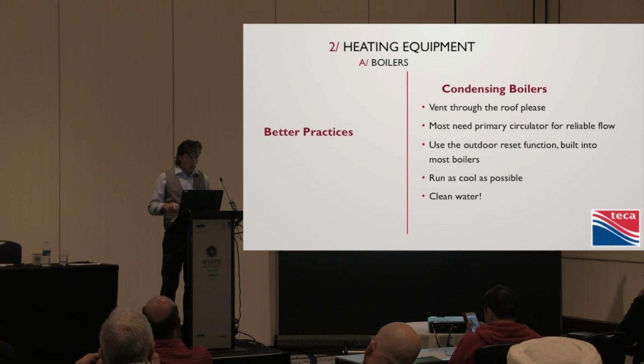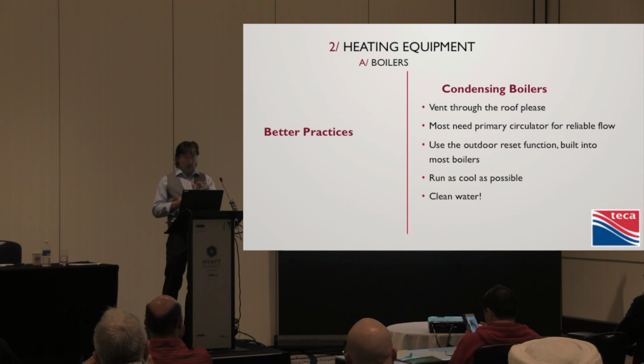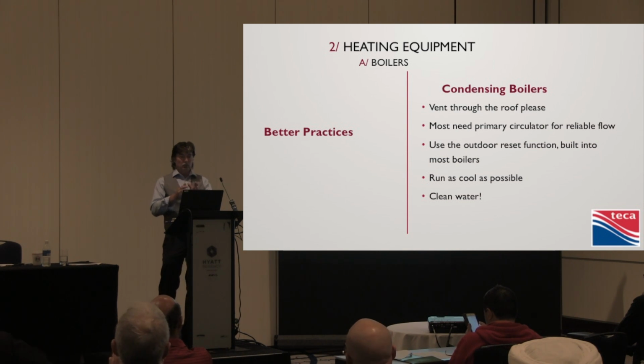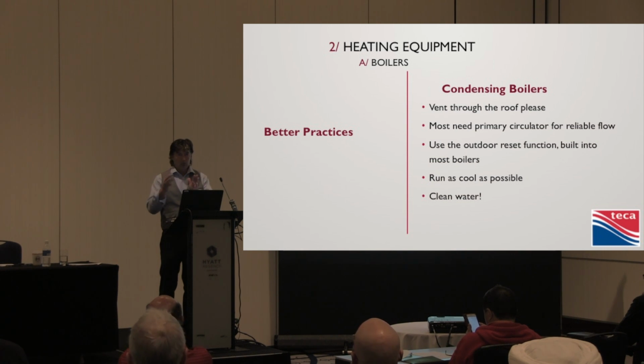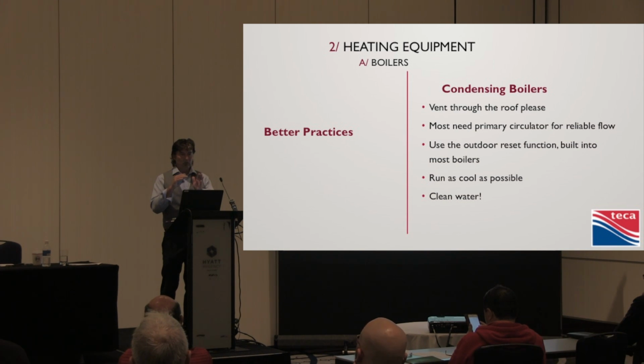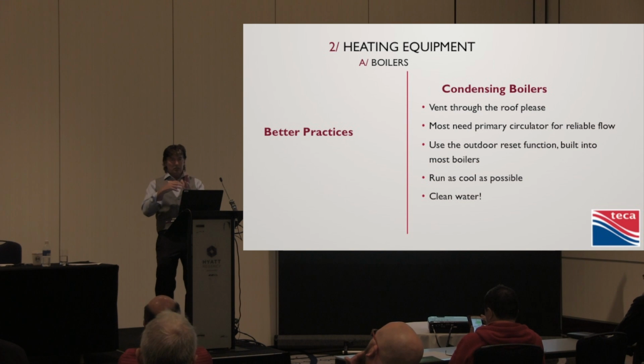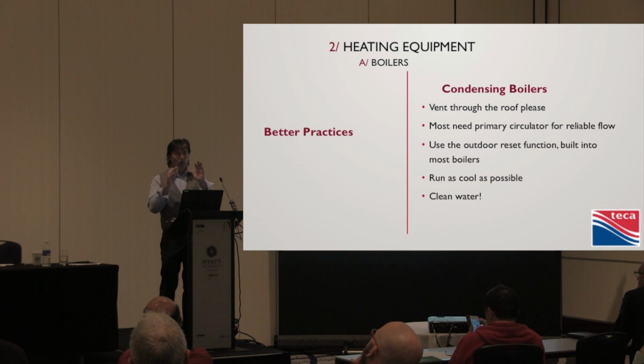Because those things are such low mass, they usually have a dedicated circulator that does only the heat exchanger of the boiler. So in the situation where you have the 5,000 square foot house and one zone open, that's not a lot of flow either, is it? In fact, that 5,000 BTUs is below a 100,000 BTU 10 to 1 turn down ratio. It's only 5,000 BTUs. So we can't be slowing, you know, if our pump is sized to flow a whole house and we only flow a fraction of that through the boiler, it can't deal with this flow.